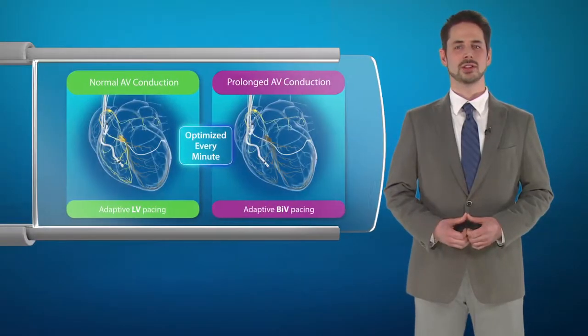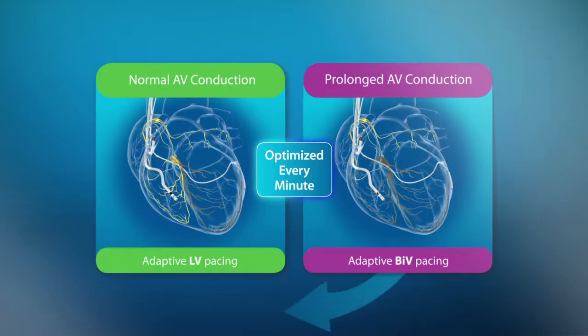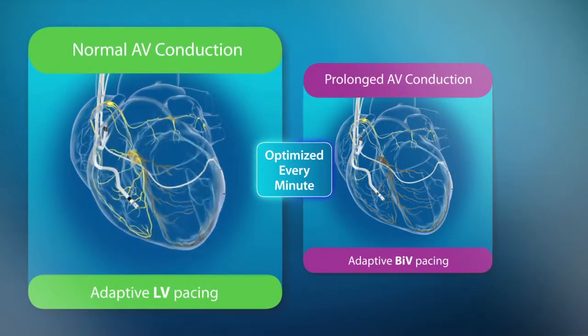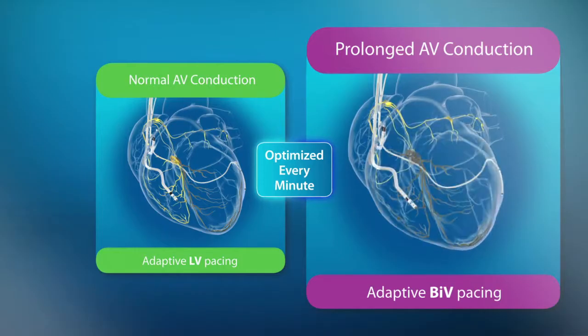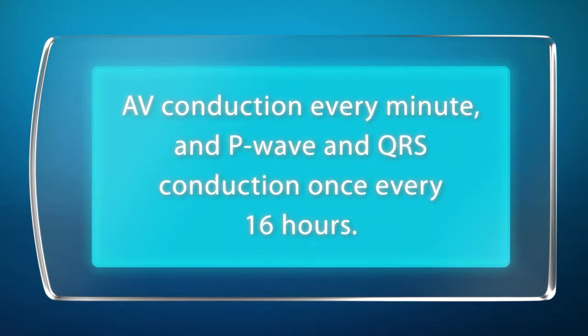Medtronic's response to the need for simple and efficient CRT optimization is Adaptive CRT — the industry's only algorithm that continuously and dynamically optimizes CRT pacing method and AV and VV delays. Adaptive CRT monitors a patient's rhythm, and if it is regular, measures three intrinsic conduction intervals: AV conduction every minute, and p-wave and QRS conduction once every 16 hours.